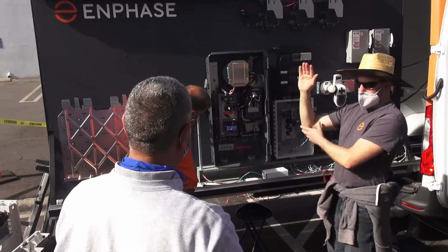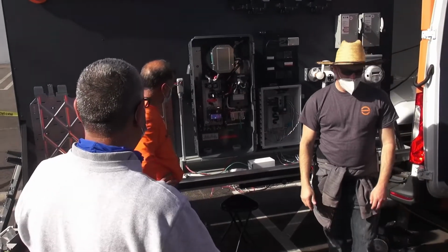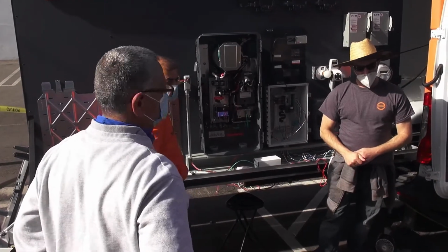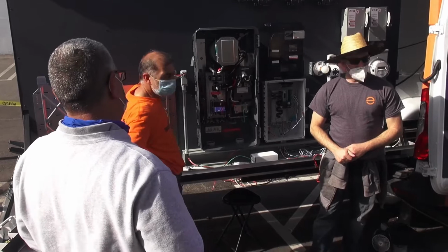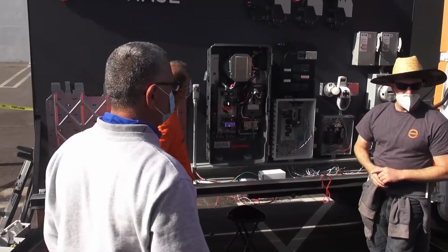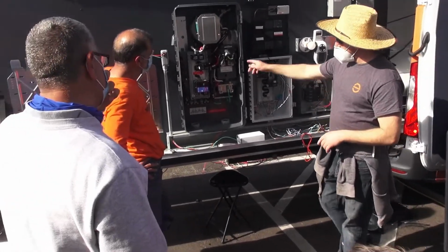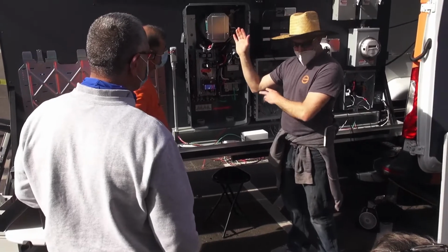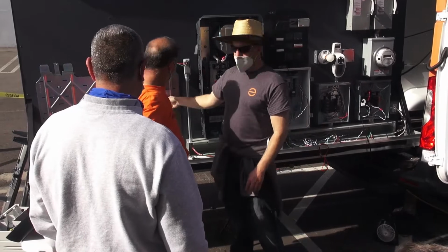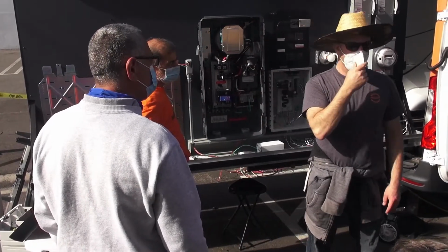If you guys just remember to have that here before you power this up, you'll be happy. Cool. And after the power's on, you don't need to touch this. It's just during the initial first-time commissioning, unless you made a mistake. The only other time you would on purpose put this in bypass mode is if you were installing all this equipment and you forgot the batteries or something, or if you're on the phone with us doing some troubleshooting.